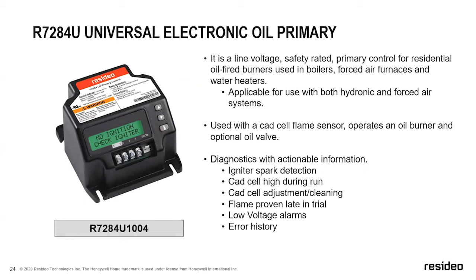You can see that it's got a digital display there, which is really nice. It does provide plain language to the installer and the service technician. It's used with a CAD cell flame sensor. It operates on an oil burner and optional oil valve. The beauty here of the CAD cell is that when the unit's actually running, you can get the CAD cell resistance, the amount of ohms it's reading. You don't need to bring out a meter or disconnect any device to see what the resistance is. It'll tell you right on the display.